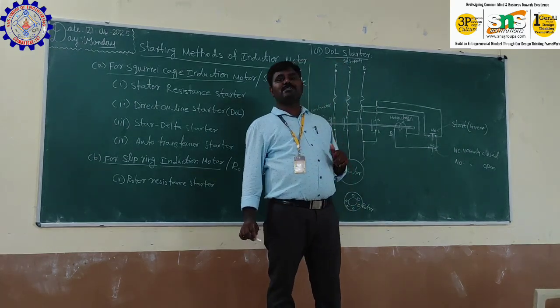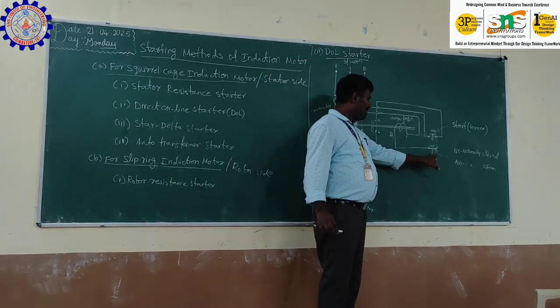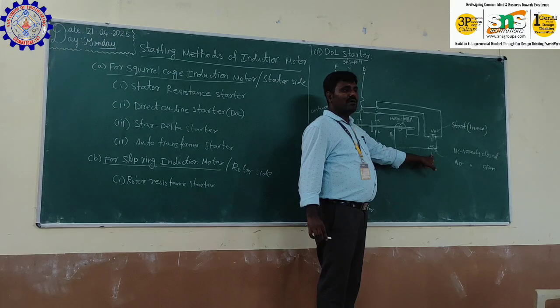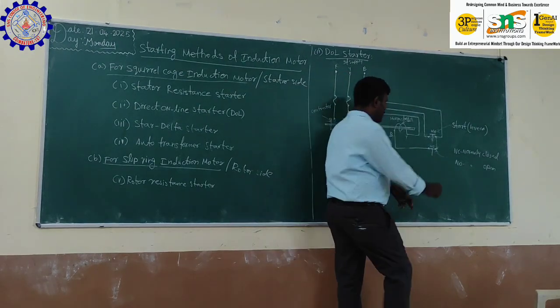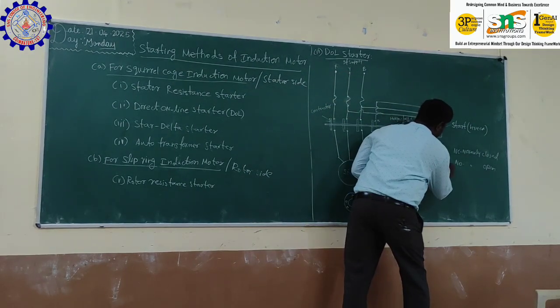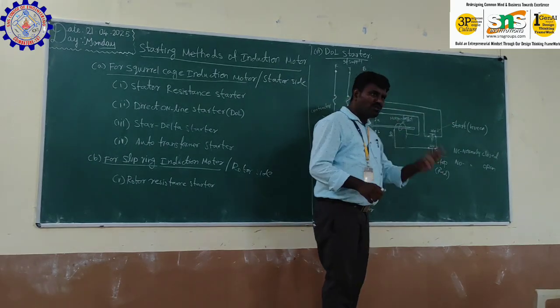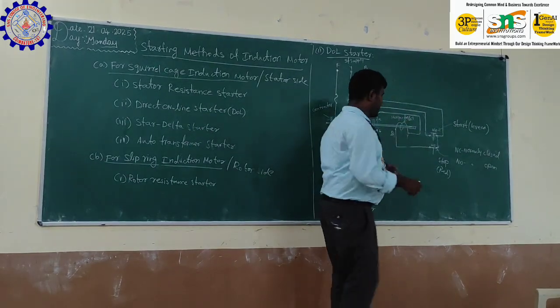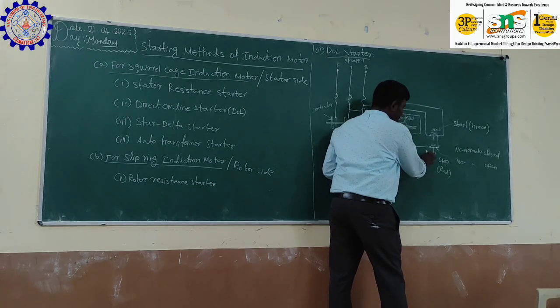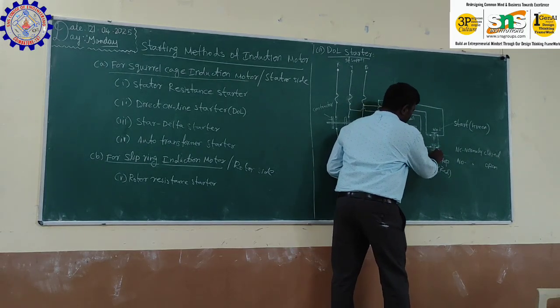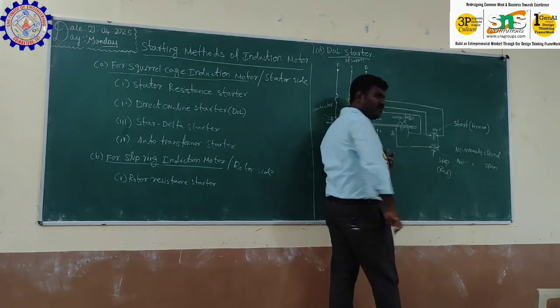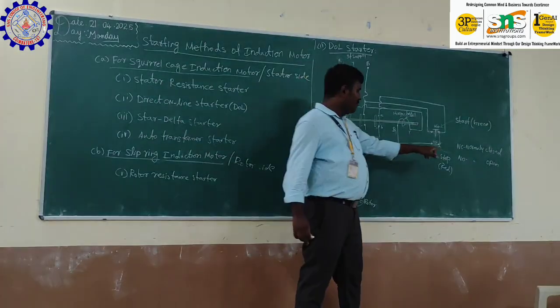If I want to stop this motor அப்படினா that will be another button called normally closed, that is called stop button. That is in red color. Okay na? When the normally closed la irukum, if I want to push that button, இது என்ன ஆகும், downwards move ஆகுமா, it moving in downwards. So downwards move ஆகும்போது இந்த ரெண்டு கான்டாக்ட் நடுவுல கேப் வந்துருமா. So it will be open circuit.